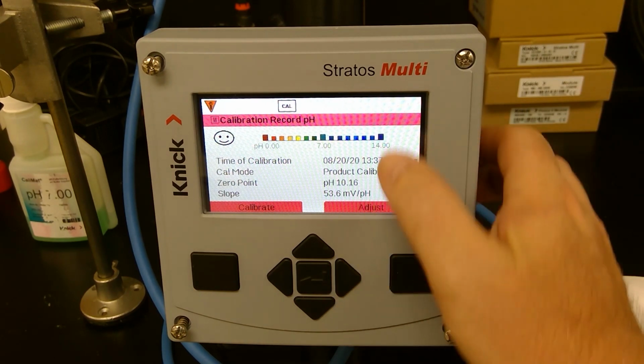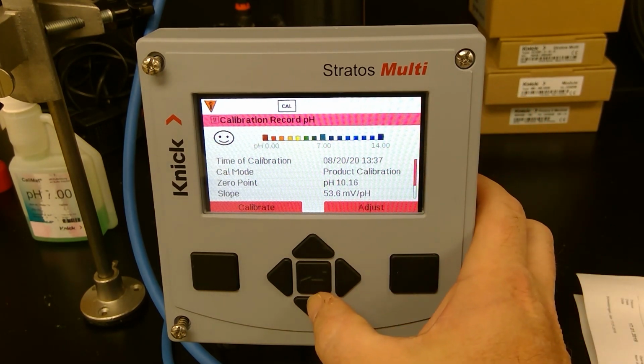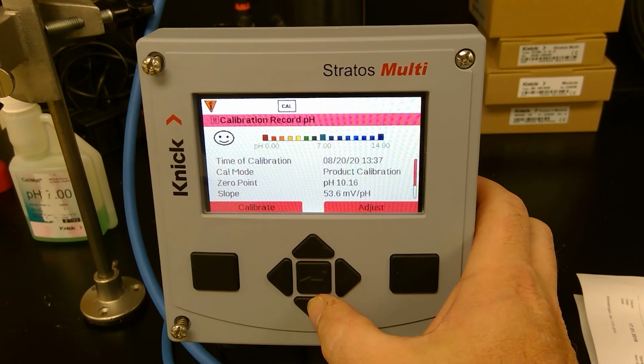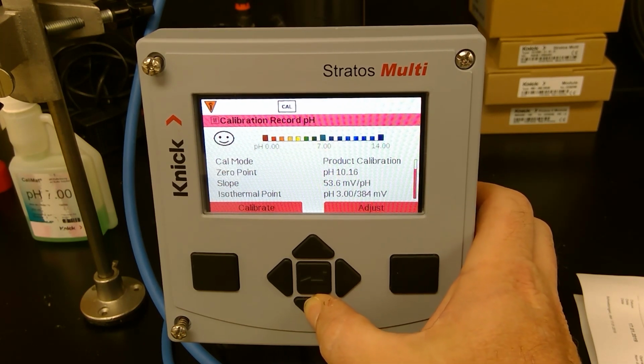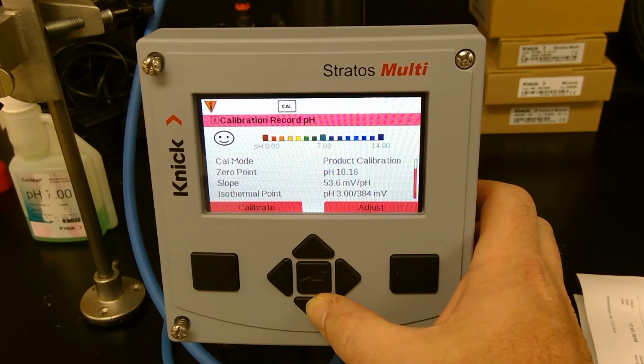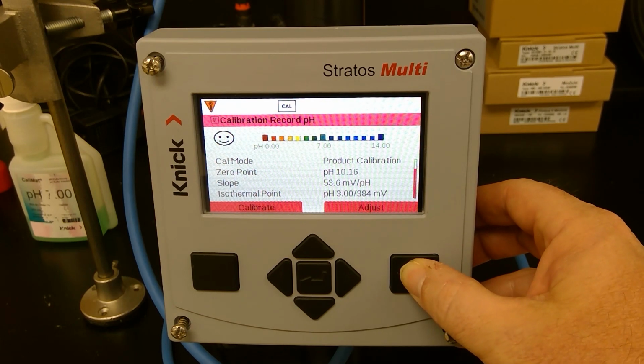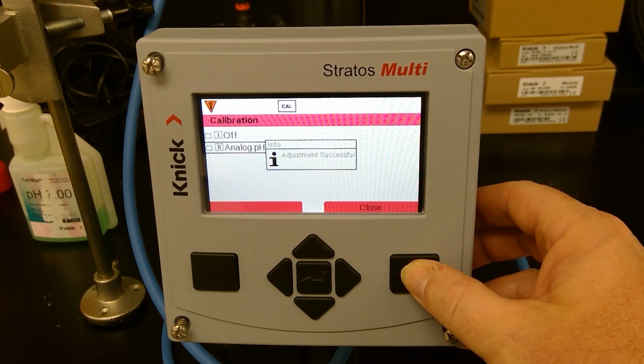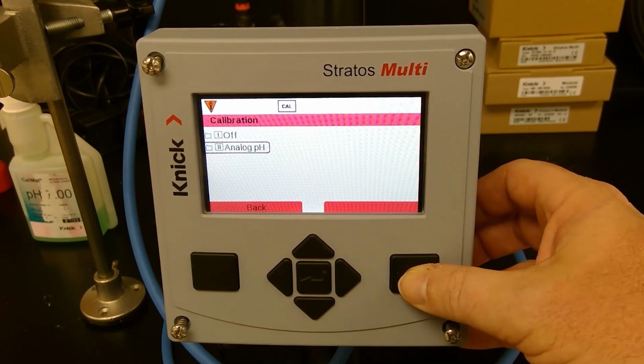So now you can see it's telling me that I'm doing a product calibration. My 0 point is 10.16. Slope is 53.6 millivolts. Isotherm point is 3. So I'm going to go ahead and say adjust. Adjustment successful.